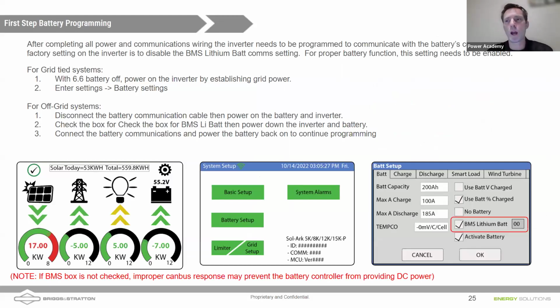So let's assume we've completed our wiring. We've got everything ready to go. What we're going to do is tell that Sol-Ark inverter to expect a communicating lithium battery. This is quite easy for grid-tied systems, because when you connect grid and power on that grid connection, the inverter should come on. Now, it's not going to turn loads on automatically. You have to hit the start button on the left side of the inverter to get loads to turn on. But the inverter itself will come on, and you can program it. If you're in an off-grid setting, you could start the inverter up with a generator, or you could disconnect the communications cables for the batteries, and then turn those batteries on to turn the inverter on.